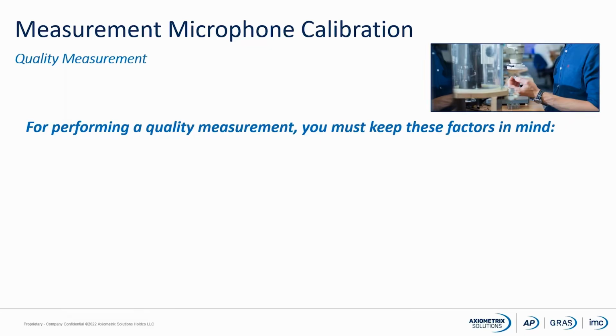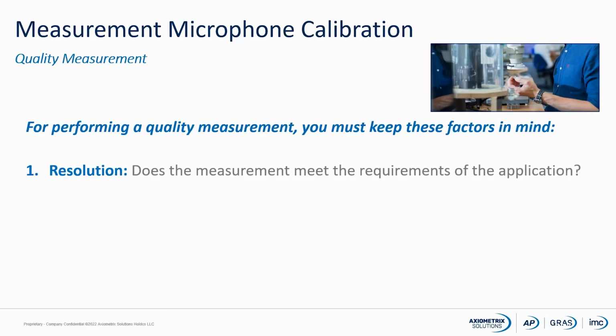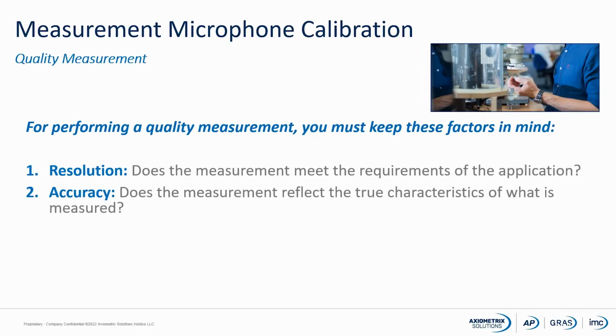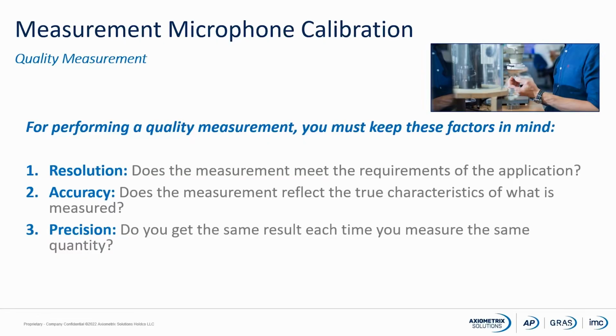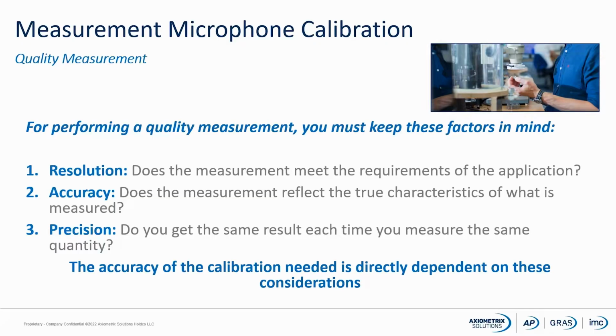For performing a quality measurement, we must have the factors coming up here in mind. First of all, the resolution. Does the instrument meet the requirements for the applications? Do we have enough digits to measure whatever we would like to measure? Accuracy. Does the measurement reflect the true characteristics of what is measured? Precision. Do you get the same result each time you measure the same quantity? The accuracy of a calibration needed is directly depending on these considerations.